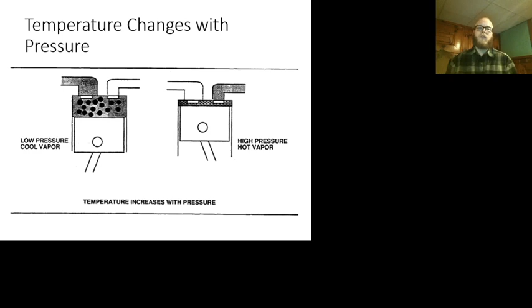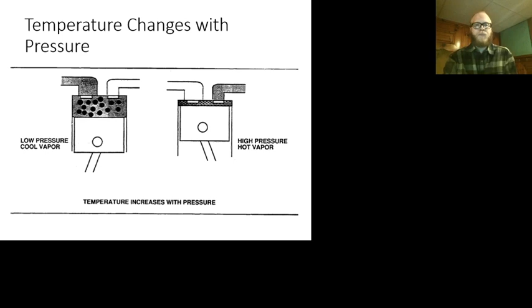We can only pull in vapor refrigerant and put out vapor refrigerant because we can compress a vapor. Think back to our braking systems, Pascal's law. I cannot compress a liquid, so if I pulled liquid refrigerant into my compressor, that would be bad because the piston's going to move up and eventually it's going to run out of room, and the liquid's going to be there and it's not going to move, and the metal of the compressor is going to move before the liquid of the refrigerant. So you want to make sure it's always vapor coming in and going back out.